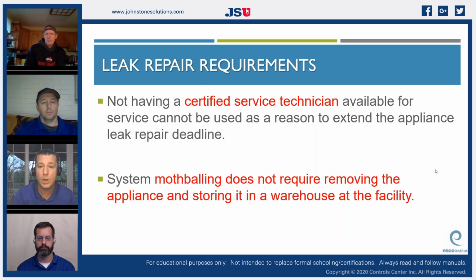System mothballing does not require removing the appliance or storing it in a warehouse at the facility. So what we talked about with mothballing is if I have a system that has multiple compressors, and I have a leak on a gasket on one of my compressors. On our larger pieces of equipment, we have service valves at the suction side and the discharge side of our compressor. And if we have an oil balance line going between the compressors, we have a place to isolate our oil right there. And even if we have a crankcase pressure balance line going between the compressors, we have valves to isolate that. So what they're saying is if you can mothball, if you can isolate that system, you're okay. The downfall is we now lose the capacity of that compressor. Yeah. So you can get by, but now you're going to get by with less capacity.